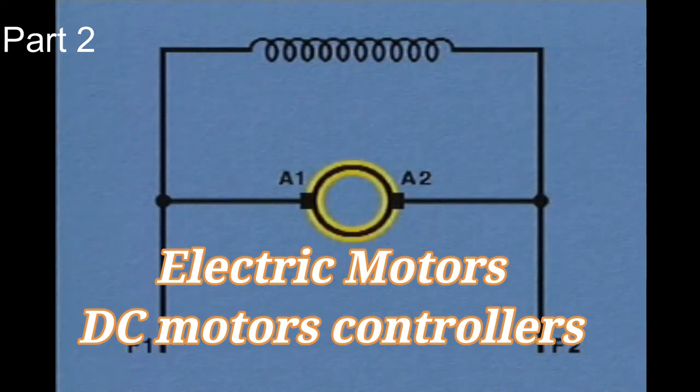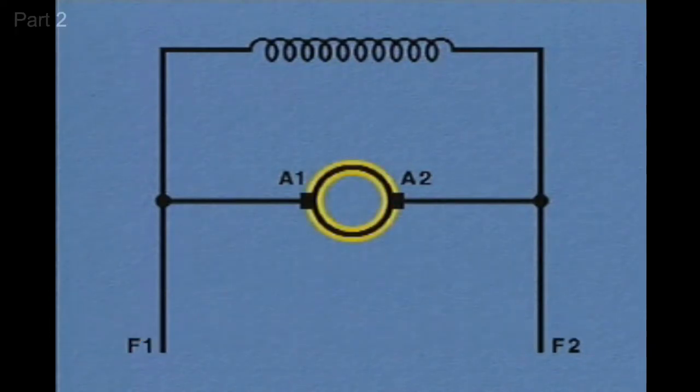Because the resistance of the armature in a DC motor is very low, it's important to always install resistance in series with the armature before starting a shunt motor.